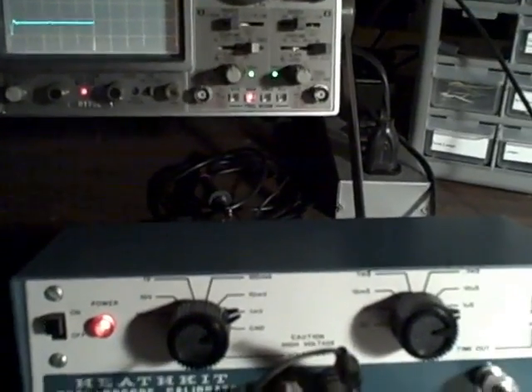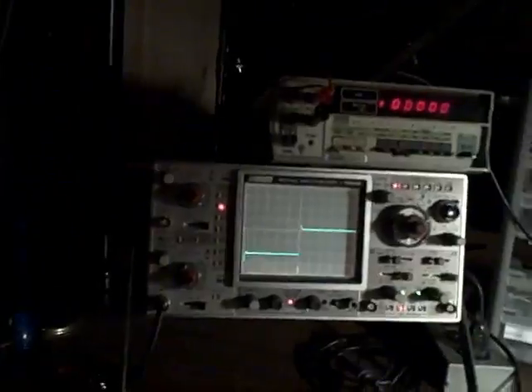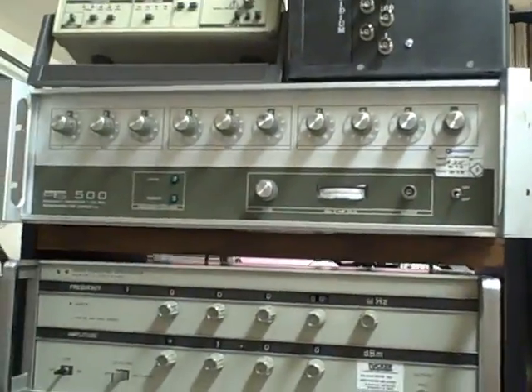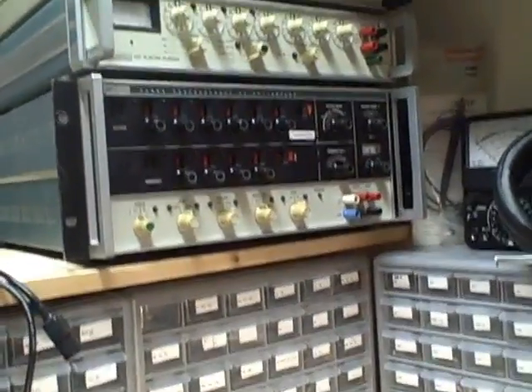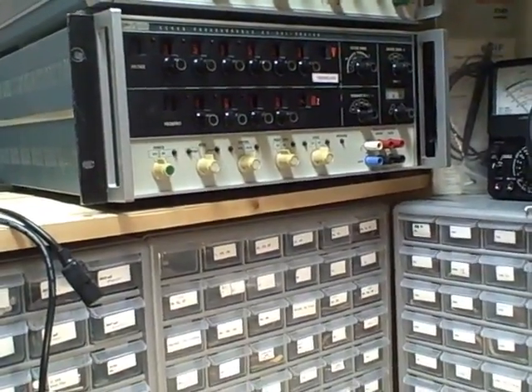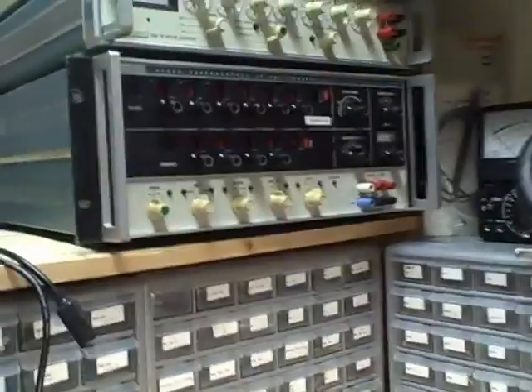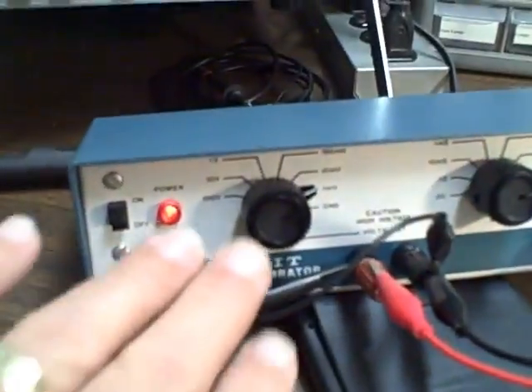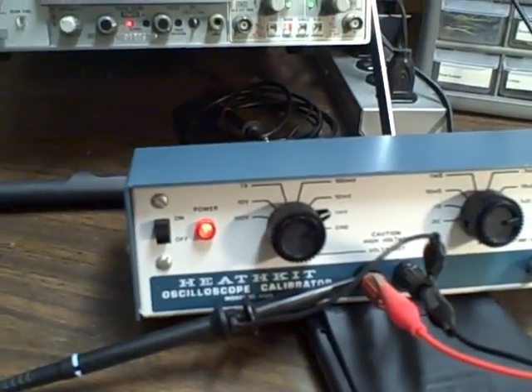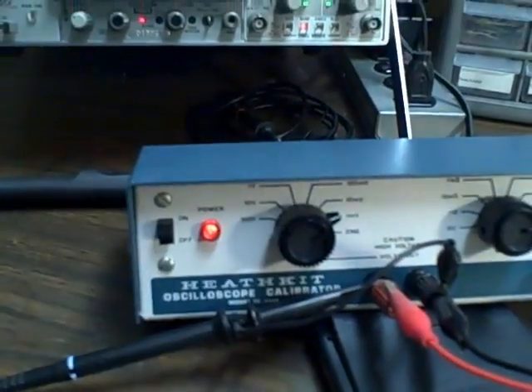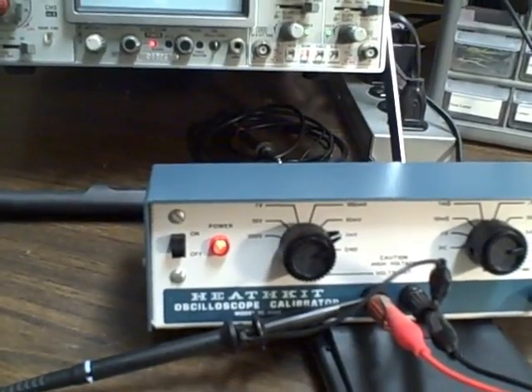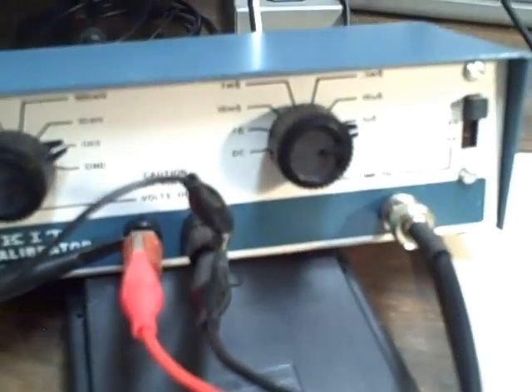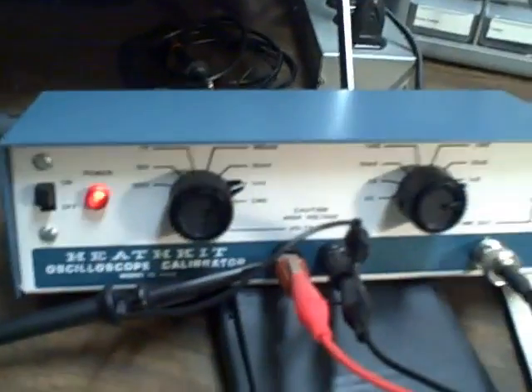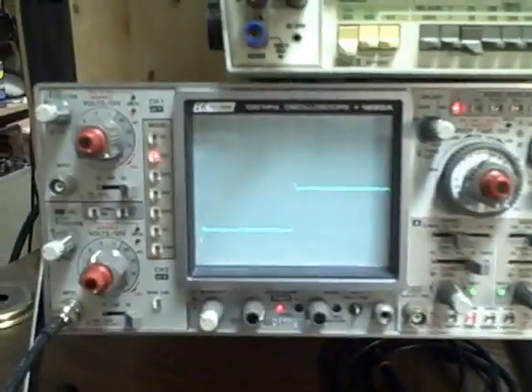Now, you don't have to have a little unit like this. You could buy yourself a room full of fancier equipment. Do the same thing. There's some voltage calibrators over there. The bottom one is a Fluke AC calibrator. The one on top of it is a DC calibrator that basically does this same thing as this, except a lot more accurately maybe and with more range, but same thing that this first style does here is provide DC voltages accurately to the output that you can calibrate to. These frequency generators right here are digital generators. Basically, this side of the calibrator provides what those do. So in this smaller, less expensive box, you got what you need to calibrate your scope.